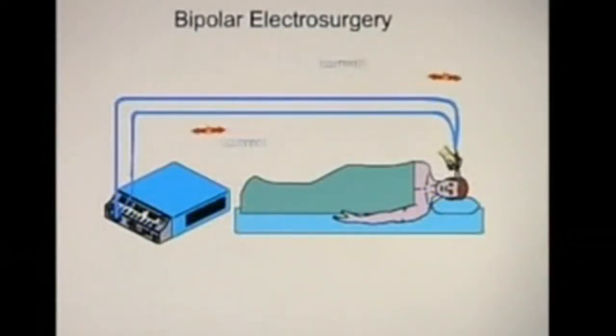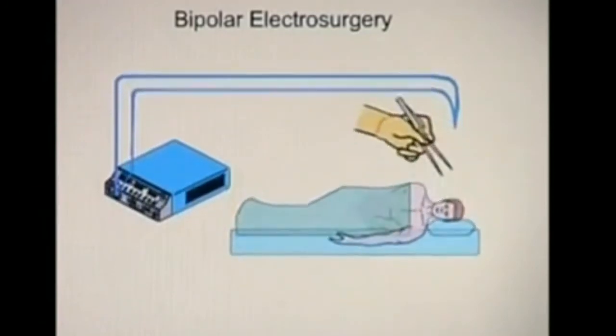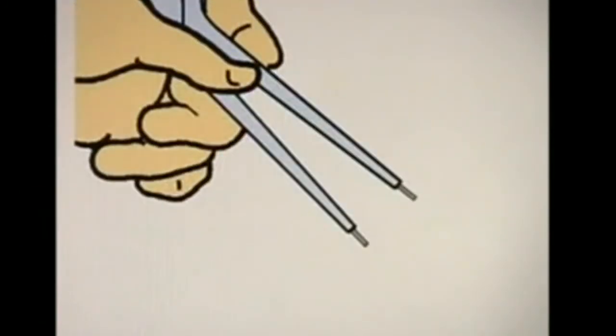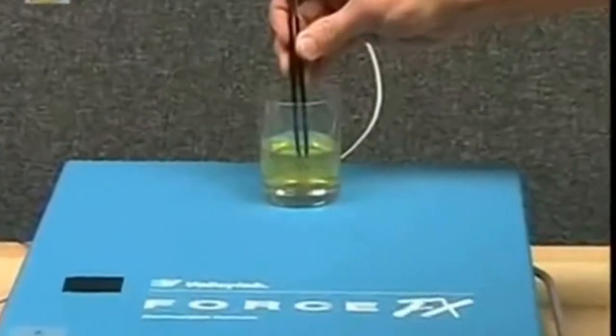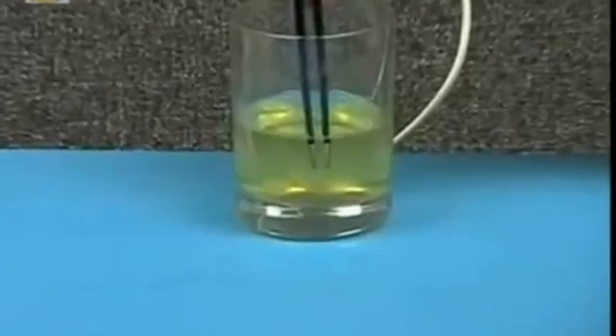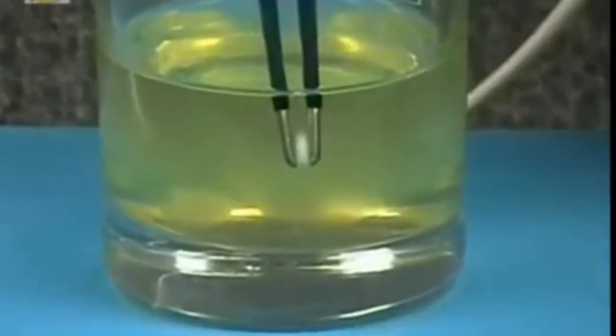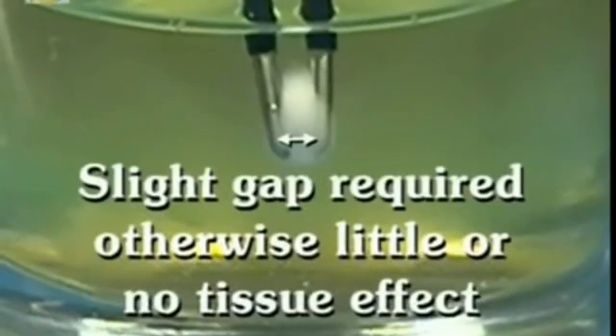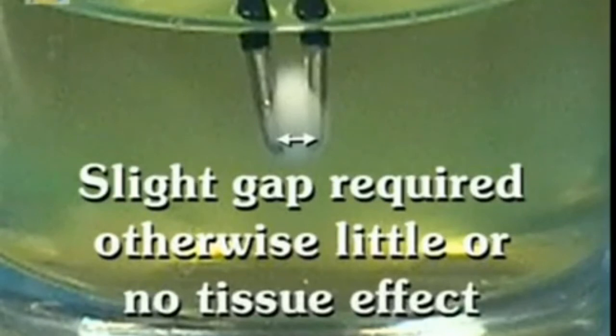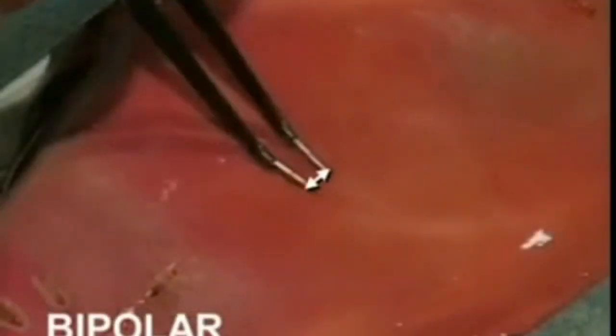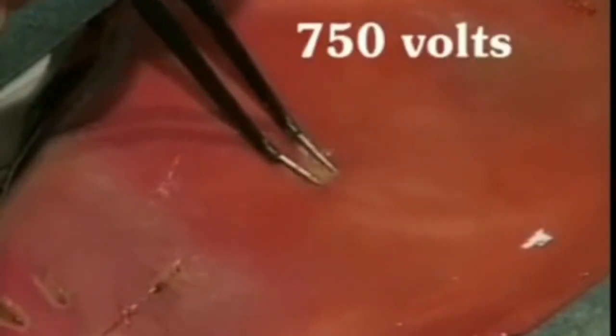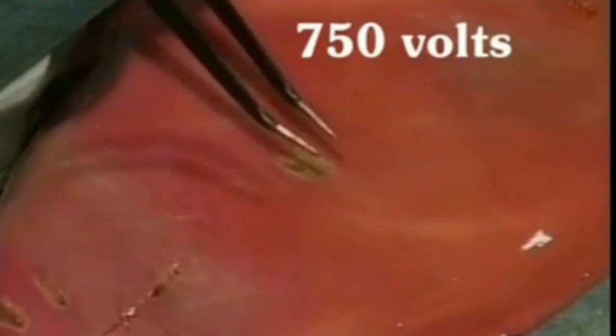Bipolar electrosurgery is when the active output and patient return functions are both accomplished at the site of surgery, and the current path is confined to the tissue grasped between the forceps tips. As demonstrated here, where we see a bipolar device being applied to egg white, bipolar is useful as it provides precise controlled desiccation, causes a limited amount of tissue to be impacted by the current, and works well in irrigated environments. Bipolar also uses some of the lowest voltages in electrosurgery, with peaks of up to around 750 volts.